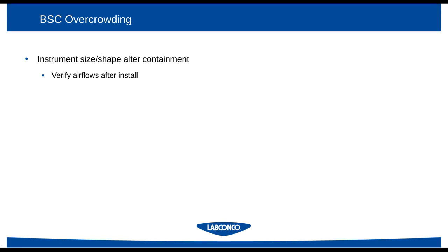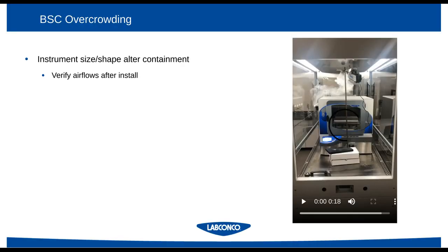So if we look at overcrowding of a biosafety cabinet, really two factors come into account. The first one is the size, and the second one is the shape of the instrument. Certainly, the instrument has to fit inside the biosafety cabinet to be a successful installation. But after that, you also have to ensure that the smoke or the airflow is going to generate a smooth path around the instrumentation. In this image, this is a view of a laminar airflow product from Labconco. And if you click play on your own, you will be able to see some of the smoke flowing through the enclosure around this large item.